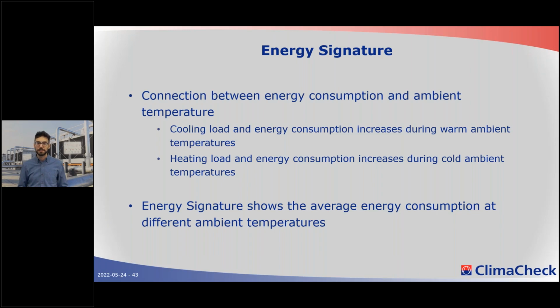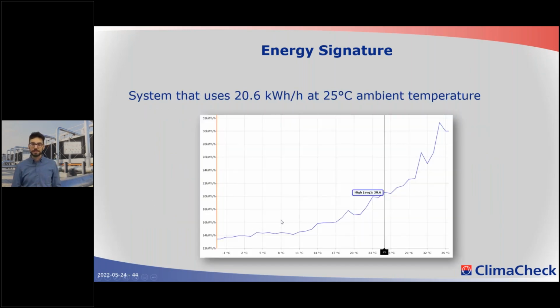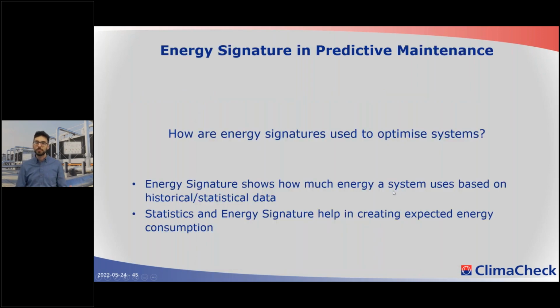This connection is the energy signature, and for this case it looks something like this: as ambient temperature increases, energy consumption increases as well. This is a typical energy signature for a supermarket system, where there's a base load we always want to cool, even in winter, but as warm weather comes, energy consumption increases. With this energy signature, we can predict that at a given temperature, the system usually consumes a certain amount of energy.